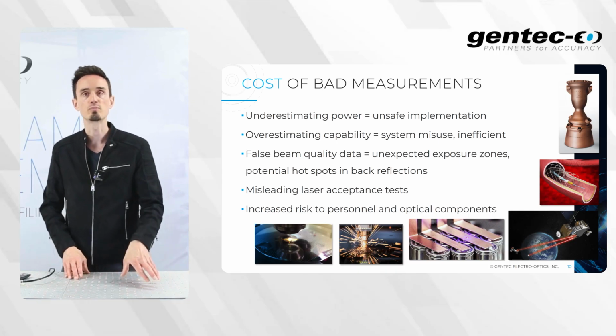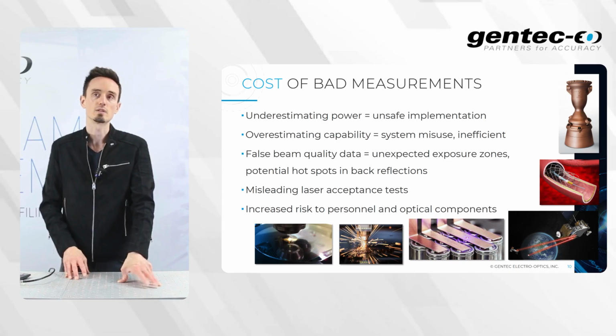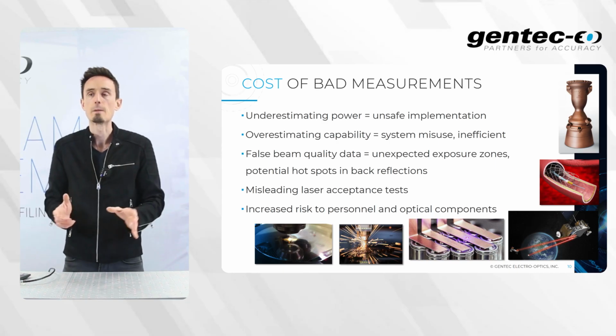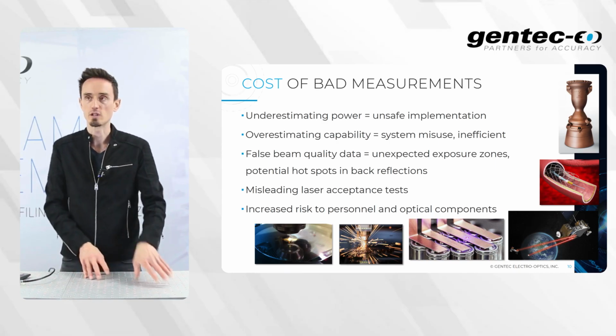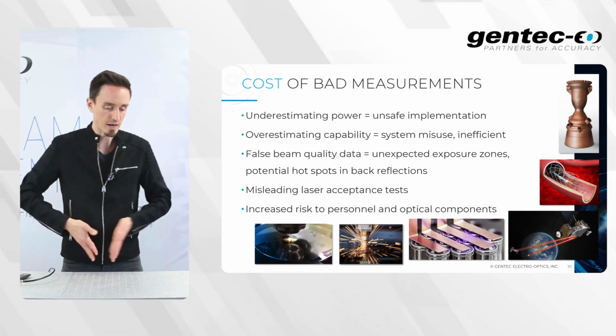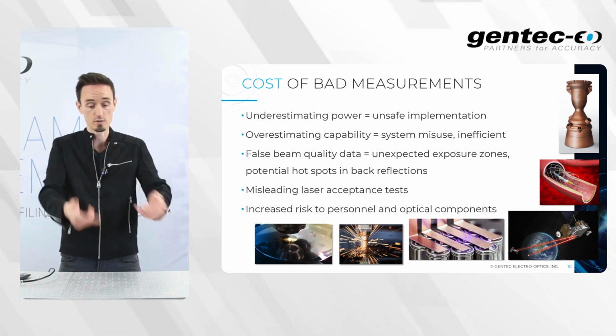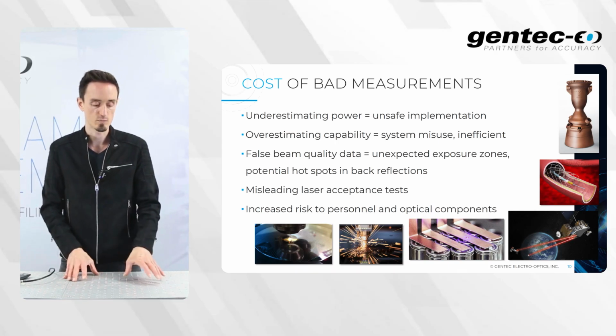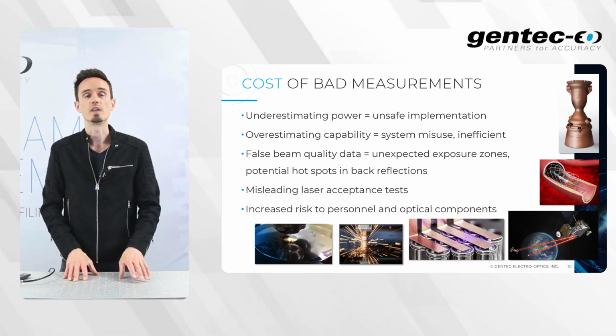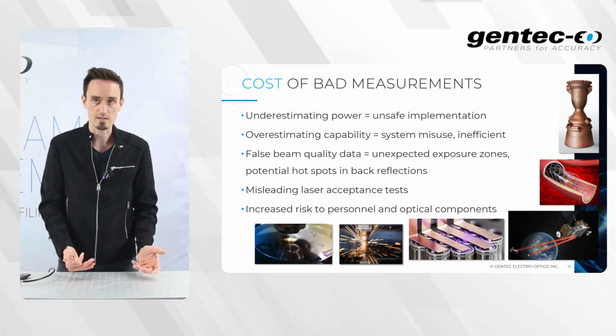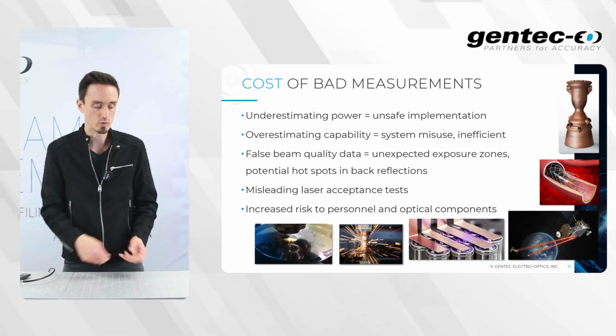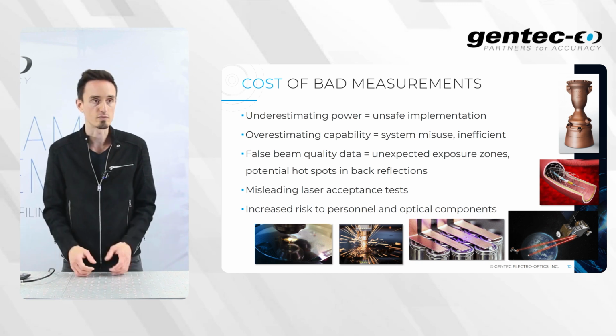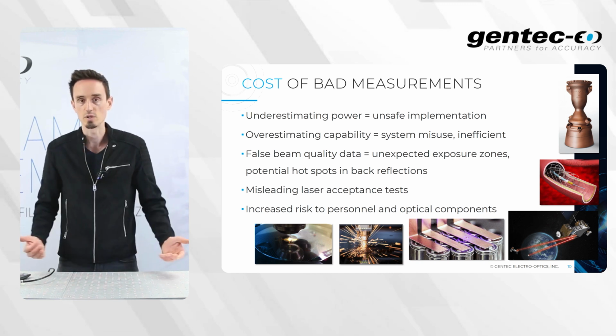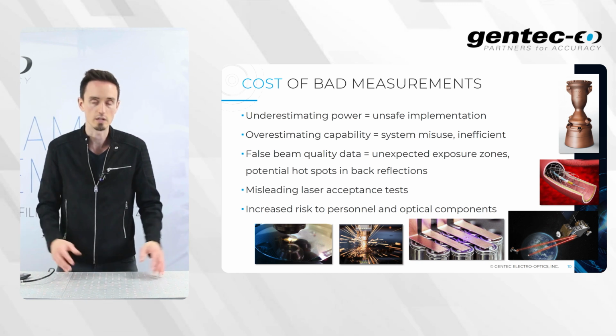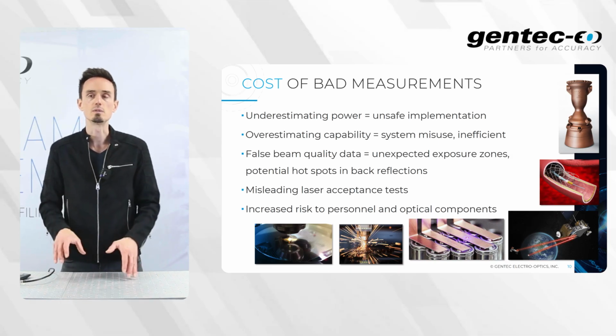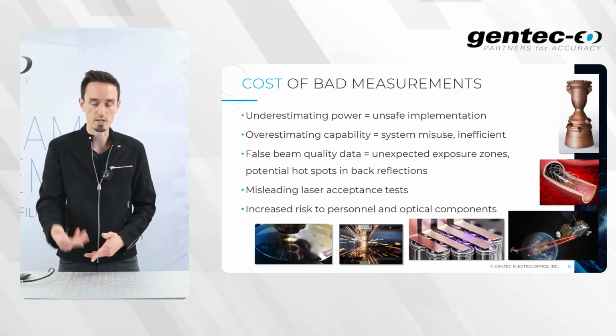Then if you have false beam quality data, I'm talking beam profiling with some hotspots and so on, that could result in unexpected exposure zones, potential hotspots in the back reflection going back to the system or to potential users, which is dangerous. Then misleading laser acceptance tests. Of course, if you have a bad measurement, you will report wrong data, and for an audit, for compliance, traceability and quality control purposes, this is not good. And the risk to personnel and optical components will be increased.